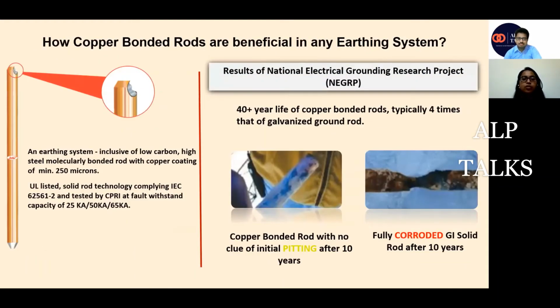Basically, if I talk about the material of copper bonded rods, as I have already told you, they have a core of mild steel, and the copper is molecularly bonded over the steel rods with a minimum copper coating of 250 microns. These rods can be customized for any fault current, from 25 kiloamperes to 65 kiloamperes. We can customize these rods and use them for our earthing system.